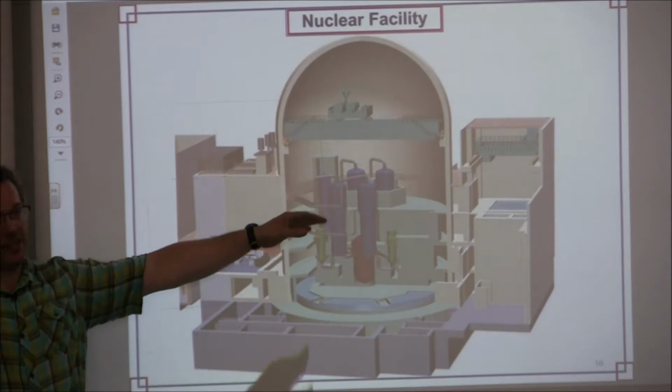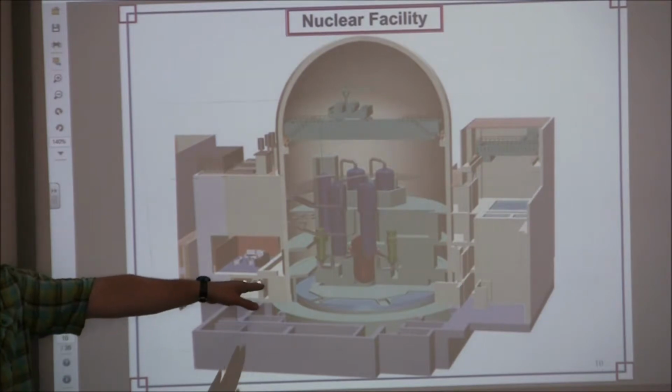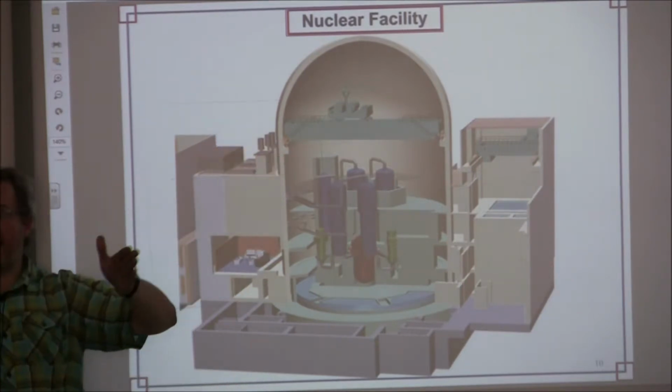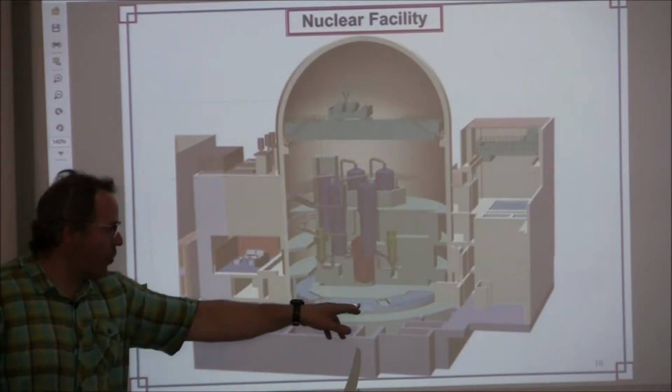And when I was at Maine Yankee, they ran a test. They had to run it every 5 years. They'd take the reactor and actually pressurize it to about 50 psi, because that's what it was designed to go without crumbling. And they say you could actually see the reactor move 2 or 3 inches, even though it's 4 or 5 feet thick concrete down here and a foot or 2 here. It actually would grow in that type of length. So it's energy. It's basically being able to contain the energy. Some people in the past have used, like you can see here, there's some water here.